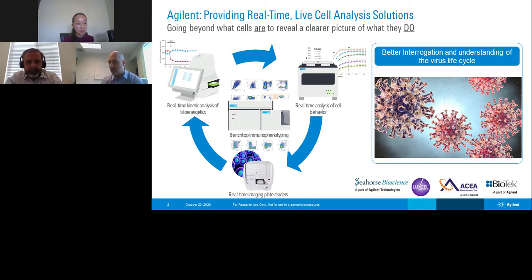In terms of imaging, the fastest I've ever gone is about 1 image per minute. I think it can go a bit lower, but one of the challenges is phototoxicity. Whether it's eSight or any other imaging system, the more frequently you're blasting cells with light, the more problems you're going to have with toxicity. And that's also very cell type dependent.